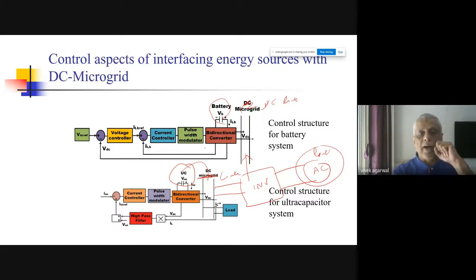You can see that this battery would regulate the VDC through these control loops. At the same time, if there are requirements of very fast transient currents, they would be supplied by the UC through this control system. That is what it supplies, and it prevents the battery from deterioration.